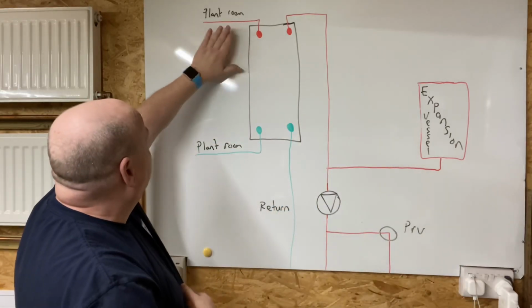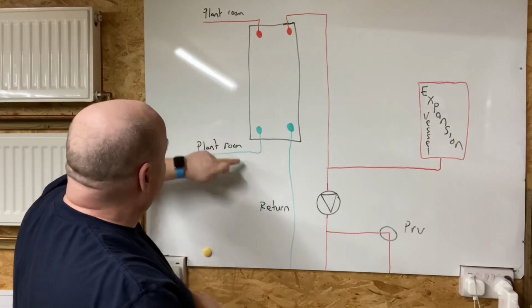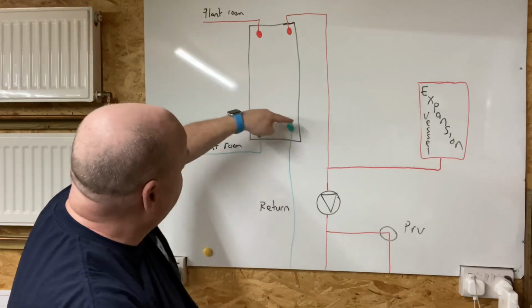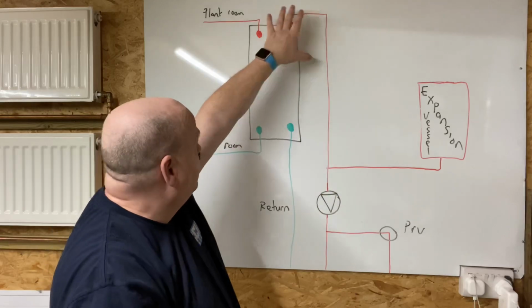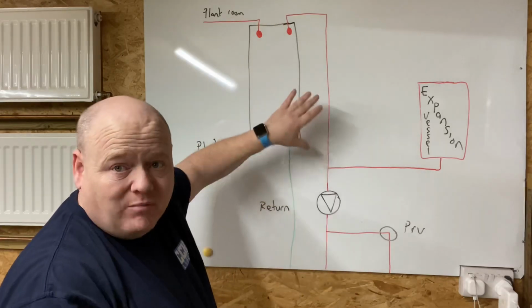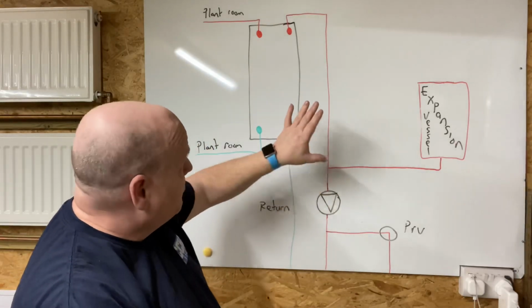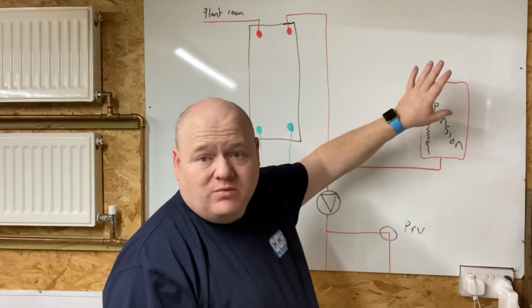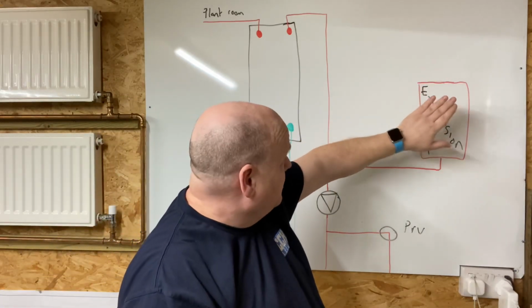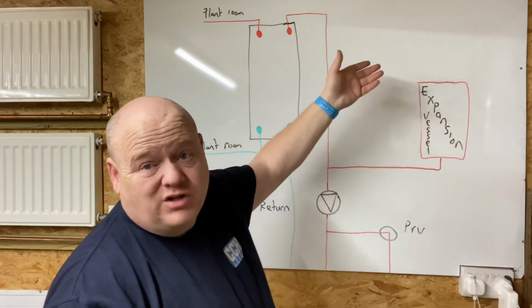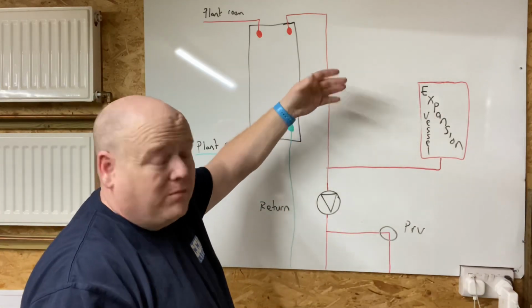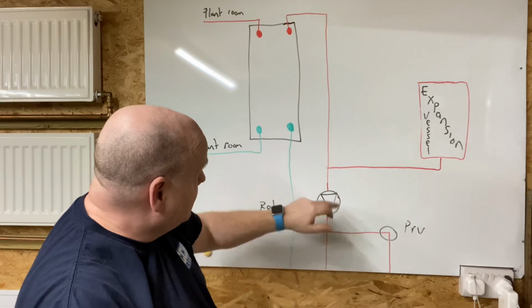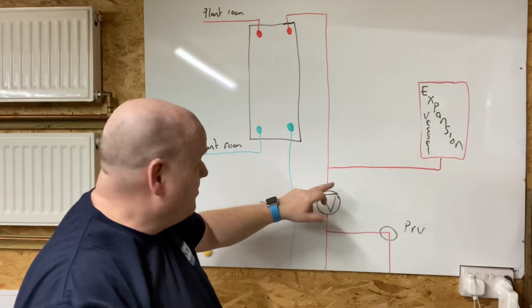So again, that's your flow and your return. They go to your plant room, but then this is the flow and return now for the central heating part of the system. But then what we need to add on to it is an expansion vessel, and that'd be sized in accordance with the size of the property as normal, like we would with any expansion vessel. And obviously that connects onto the system.